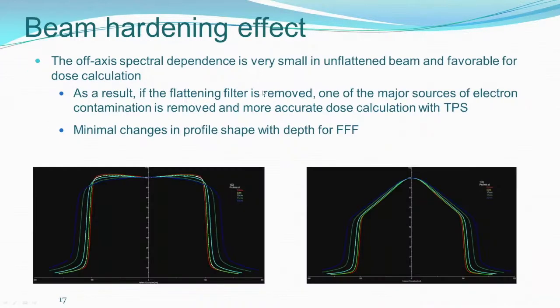And the beam hardening effect has one more thing: the off-axis spectral dependence is very small in an unflattened beam. So the spectral dependence of the unflattened beam in the off-axis is very small. The spectrum is almost the same, so it is very favorable for dose calculation. The other thing is, because you don't have a flattening filter, the electron contamination is also removed. It is also not there. So your TPS can now do a much better, more accurate calculation.